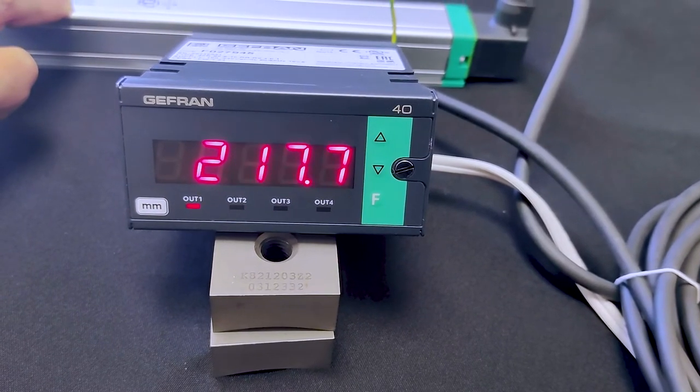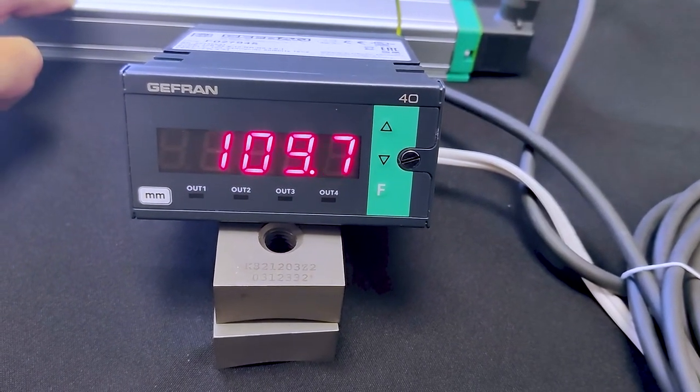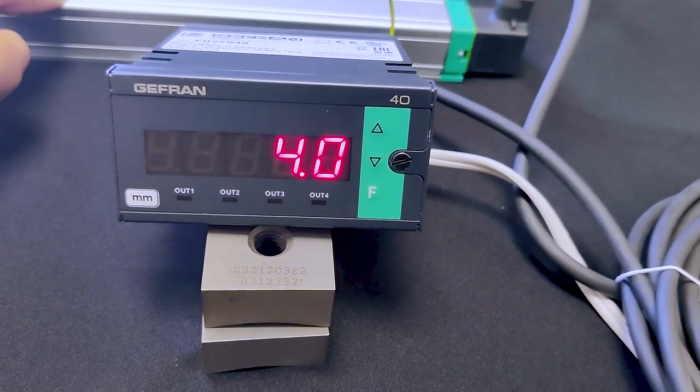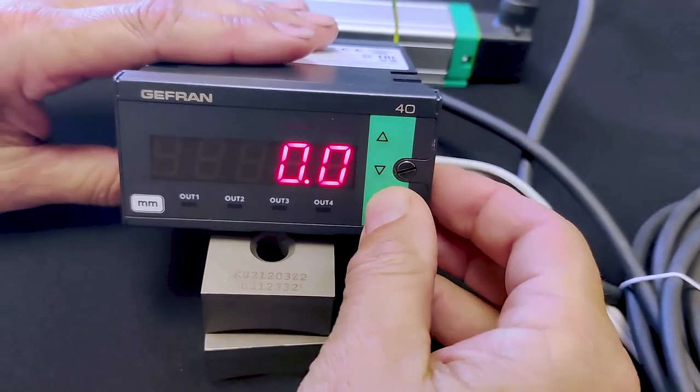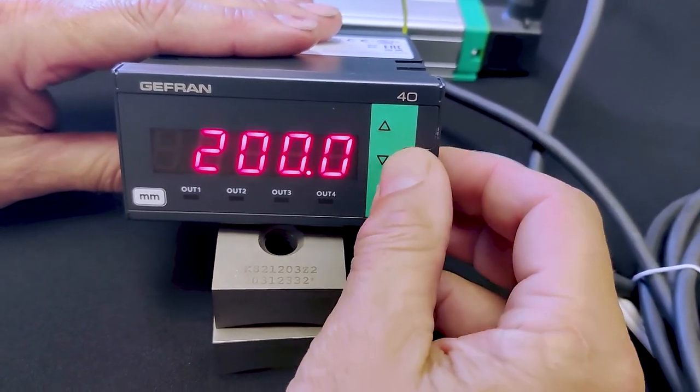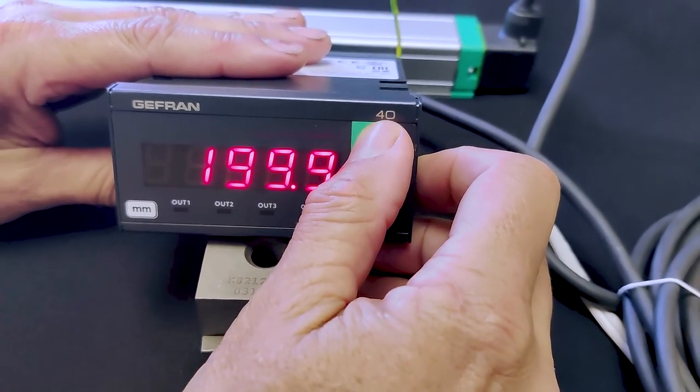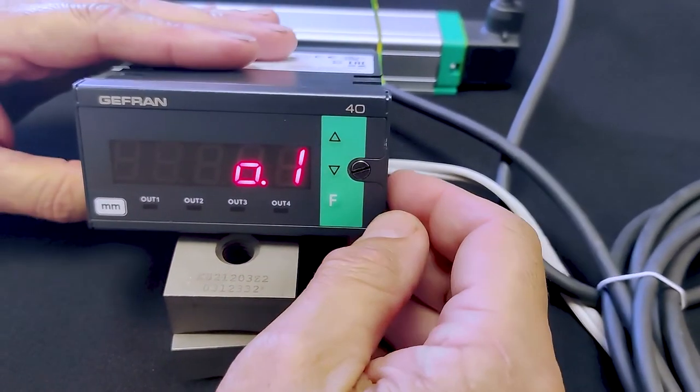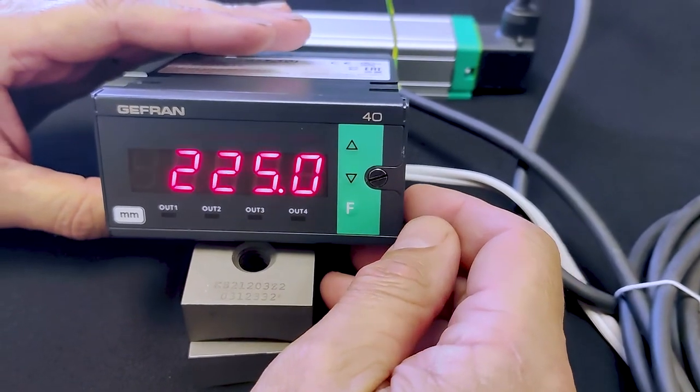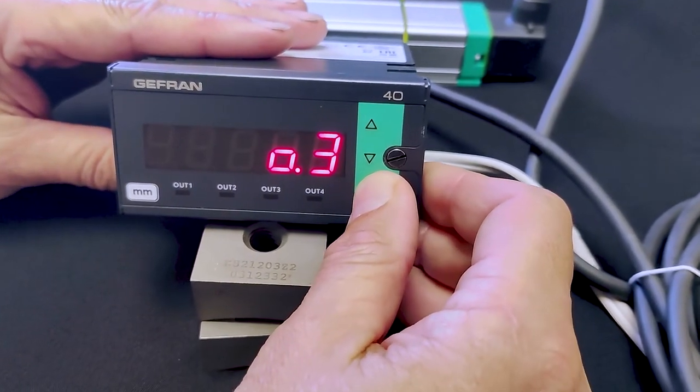They're non-latching, so as you go back they simply open back up. And those values can be changed again here at 01. You can change them to anything you want. So again, at a certain point if you want another light, an audible alarm, anything to come on, you can utilize those relays to do that.